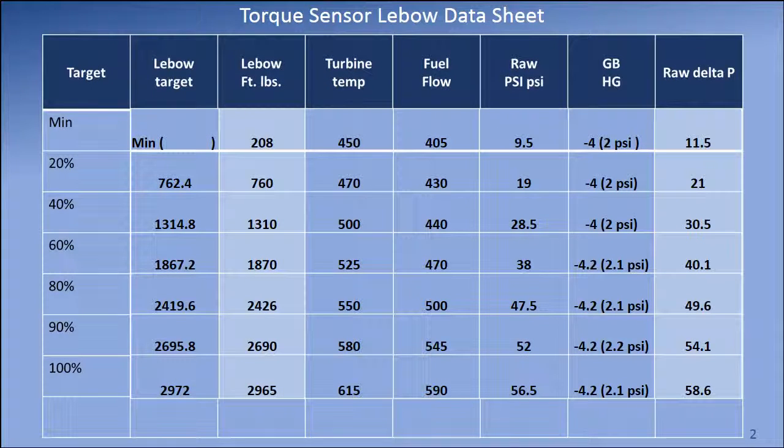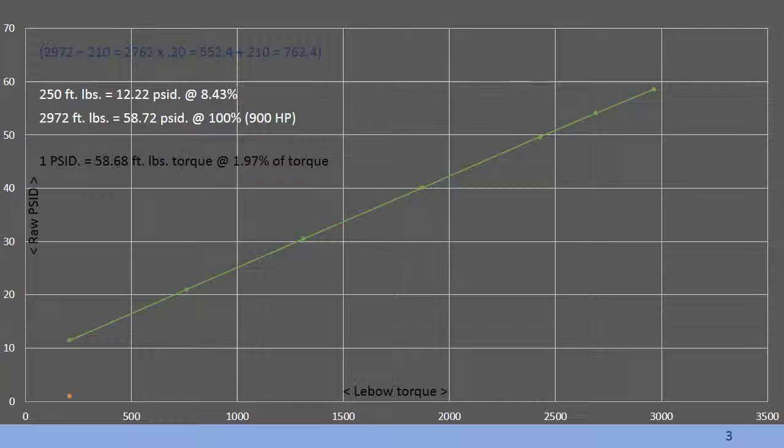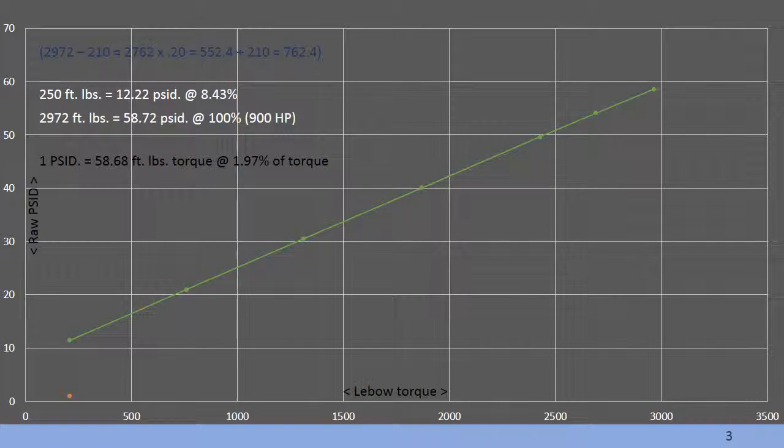This is a torque sensor LeBow data sheet that we filled out yesterday when we performed the LeBow procedure. This is a plot of the 7-point LeBow run data that we performed yesterday.